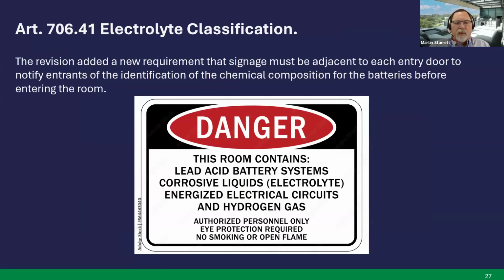Article 706.41, electrolyte classification. This revision added a new requirement that signage must be adjacent to each entry door to notify entrants of the identification of the chemical composition of the batteries before entering the room. Next slide.